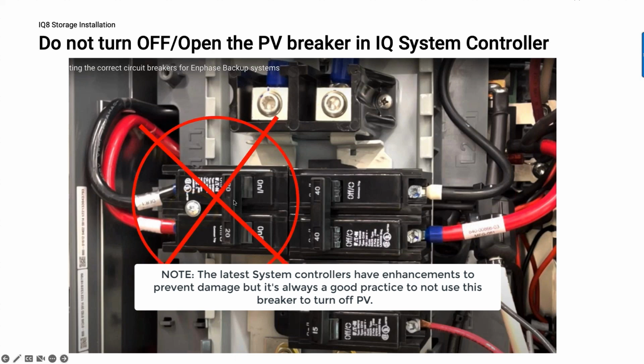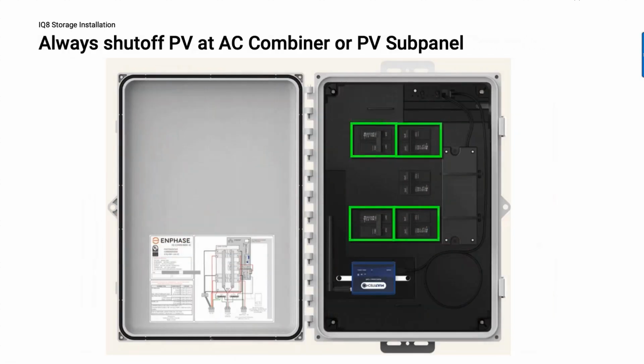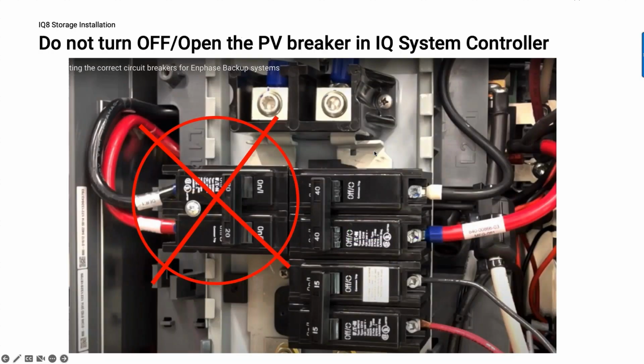So the proper way to do this is not to flip the breaker here, but actually to go to the combiner box and just flip off all of the breakers here. Now, I got a question the other time we mentioned this: what happens if this trips by itself, right? So there's a short in the line, it actually trips this breaker. Is it going to actually damage the system controller?